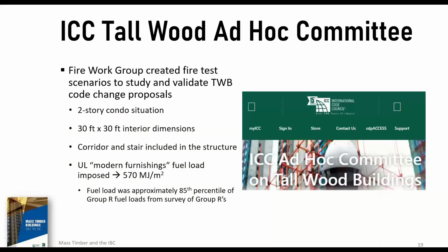So a very active work group was the fire work group. They determined that the fire tests be performed or undertaken to validate the proposed code language changes that the Tallwood Building Ad Hoc Committee put forth. So they determined that the test structure be a 2-story configuration. 30-foot by 30-foot column line is fairly commonplace in the design profession. So they went with 30-foot by 30-foot interior dimensions. They wanted to ensure that corridors and a stairwell were included in the test configuration with the structure. And they used the Underwriter Laboratories Modern Furnishings fuel load. I believe the design fuel load was approximately 550 megajoules per square meter, but the as tested conditions were slightly higher at 570 megajoules per square meter.